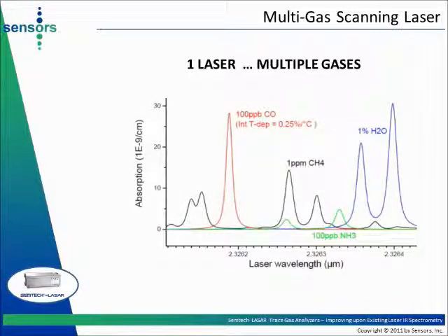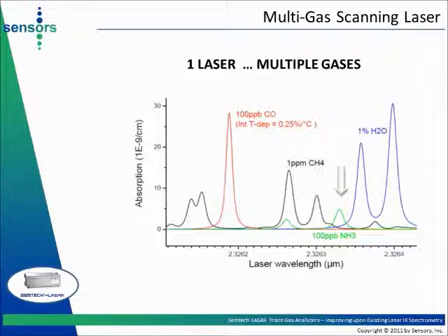A benefit of collecting 200 data point spectra instead of single wavelength intensity measurements is that more than one gas can be measured using a single laser. In this example, using a laser set at about 2.33 microns, a single scanning laser can be used for the simultaneous measurement of trace carbon monoxide, trace methane, trace ammonia, and percent-level water vapor. Many more examples can be proposed, as non-fibered lasers provide access to spectral information in the 0.6 to 3.3 micron spectral range using tunable diode lasers.